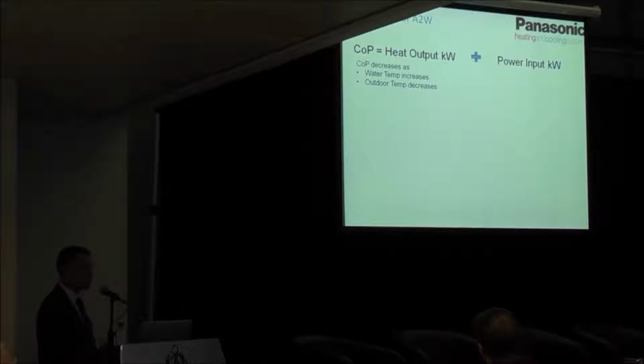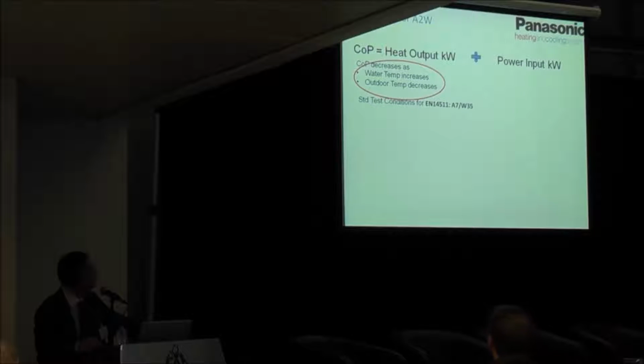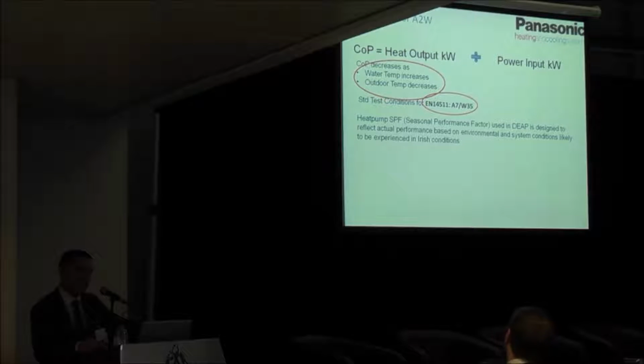A COP will decrease as water temperature increases and outdoor temperature decreases. In the test conditions for heat pumps, when we hear a unit has a capacity of 12 kilowatts or 9 kilowatts, etc., it is at air at 7, water at 35. But when we're looking at the DEAP software, we don't just look at COP at air at 7, water at 35. We look at the SPF, the seasonal performance factor, which is based more on Irish conditions. So it's across the heating season, and those temperatures are air at 7, water at 45, air at 7, water at 35, and air at 2, water at 35.